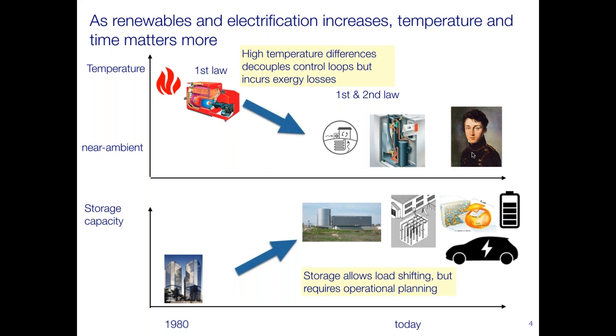In terms of temperature level, it's certainly decreasing. Compare that to 30 to 40 years ago, when we primarily burned fossil fuels to heat buildings—temperatures were relatively high, which had the advantage of decoupling control loops between generation and consumption, but it also incurred energy and exergy losses because of those temperature differences. Now, moving toward vapor compression cycles, those temperature differences need to be reduced to increase second law efficiency, which couples control loops between generation, distribution, and consumption much more tightly.